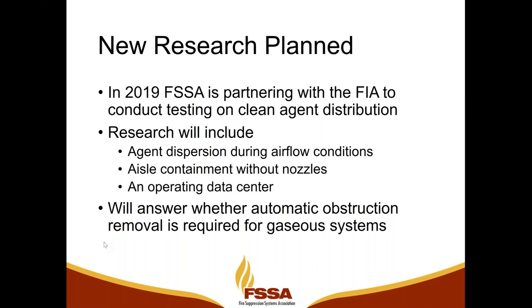So we want to let the viewers of this webinar know that in 2019, the Fire Suppression Systems Association is partnering with the Fire Industry Association in Europe, the FIA, to conduct testing on clean agent distribution. That research will include trying to determine the characteristics of agent dispersion during high airflow conditions, when aisle containment is present without nozzles, and gas flow through the equipment into the contained aisleway, and this will be done in an operating data center. So this research project is in its planning stages. There are a number of manufacturers that are going to be present and contributing to the testing.